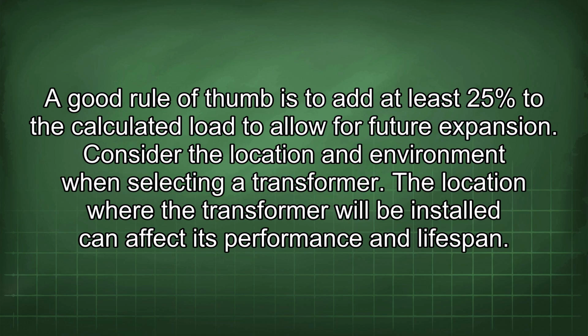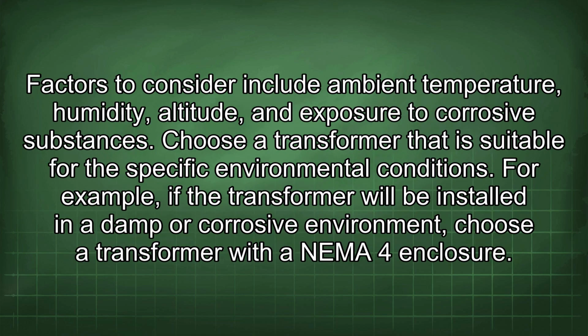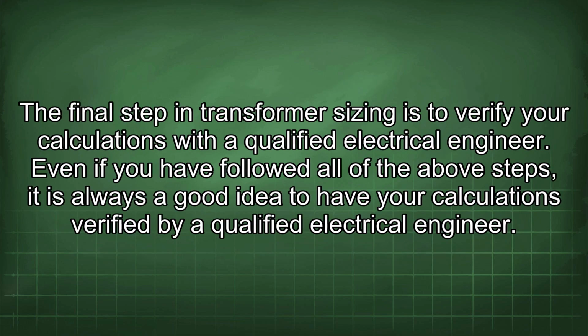Consider the location and environment when selecting a transformer. The location where the transformer will be installed can affect its performance and lifespan. Factors to consider include ambient temperature, humidity, altitude, and exposure to corrosive substances. Choose a transformer that is suitable for the specific environmental conditions. For example, if the transformer will be installed in a damp or corrosive environment, choose a transformer with a NEMA 4 enclosure.